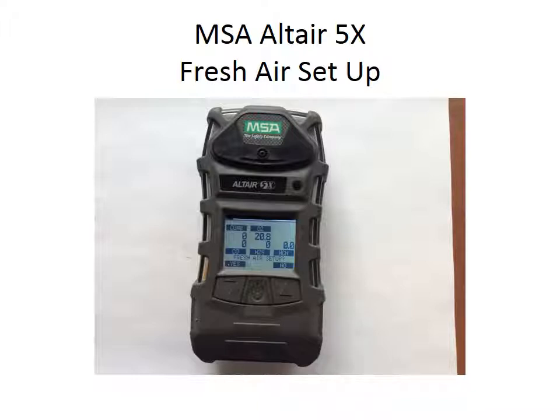A point of caution here: if you're going to hit yes for fresh air setup, make absolutely sure that you're in a fresh air environment. If you're up at the scene, you get out of the truck and you're potentially standing in a natural gas contaminated environment, you don't want to hit that fresh air setup, because basically what you're telling the meter is that this is a baseline. This is fresh air, and that's where it's going to start its readings from.